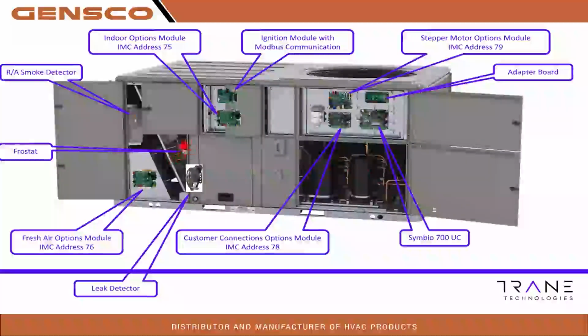Here's a frost-stat. This comes on every unit. If you order a return air smoke detector, that is going to be wired into your indoor options module. So that's going to land there if it's factory installed. I'll show you what you have to do if you have a third party smoke detector mounted in the ductwork, because we're going to wire it into the Symbio board. But this is a great picture for the board layout.